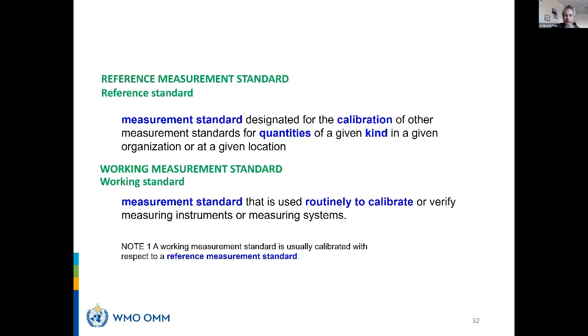The reference is a measurement standard designated for the calibration of other measurement standards. So it is that thermometer which is used to calibrate other thermometers by comparison. It's that mass that you use to calibrate other masses. Rarely do you use the primary mass standard to calibrate commercial ones. Of course, you need a reference in between.